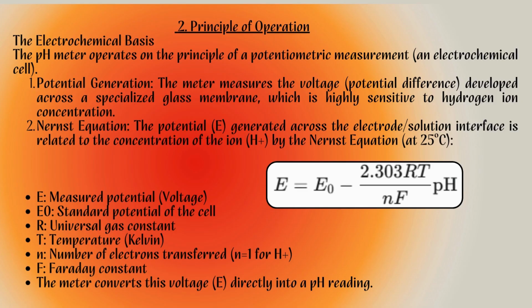This equation, which you see here, shows that the measured potential E is directly dependent on temperature and the activity of the ion being measured. The pH meter unit uses this relationship to convert the measured voltage directly into a readable pH value. This explains why temperature is so critical.